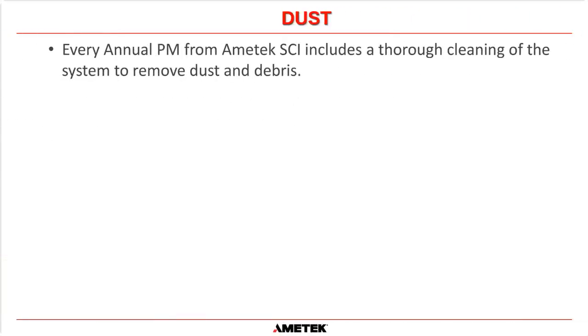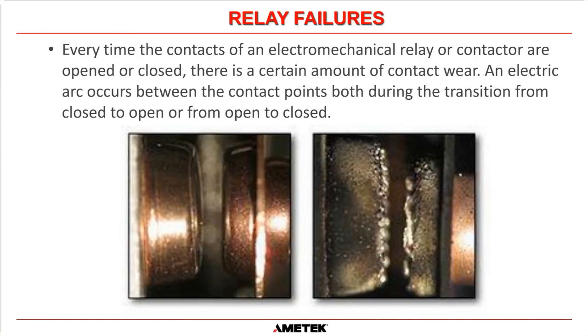And obviously, every annual PM from AMETEK SCI includes a thorough cleaning of the system to remove dust and debris. And all of our guys, especially at the Houston office, carry vacuums with them. If one of our FSEs has to fly to your plant, then we may ask if we can use your vacuum if you have one available. And if you don't, then we'll try to go to the local hardware store and buy a vacuum and leave it in that switch room when we leave, so it can be used next time we're there. But it is very important to clean out the system once a year to make sure that there's no buildup of dust.